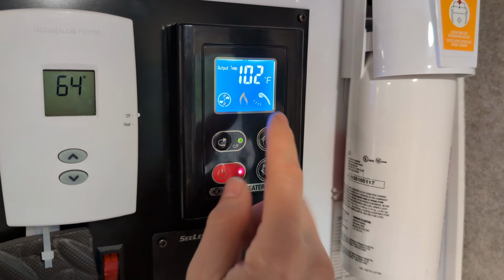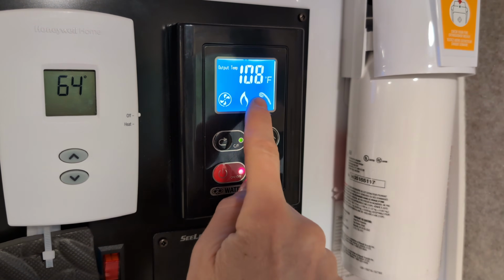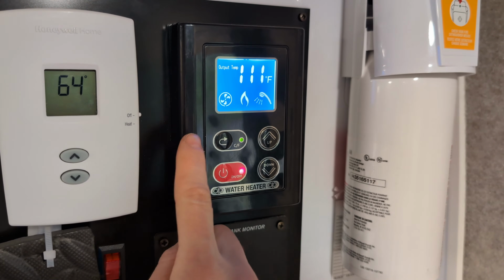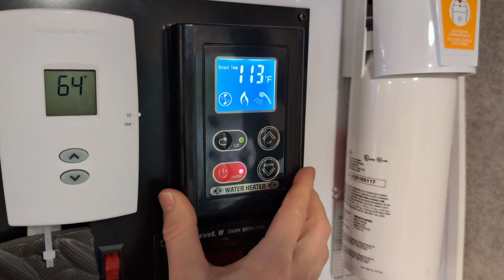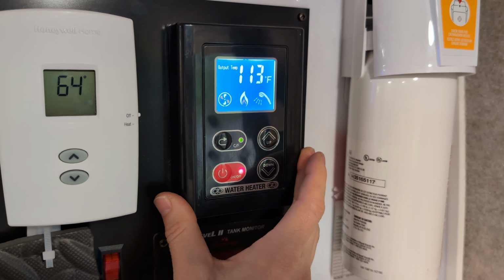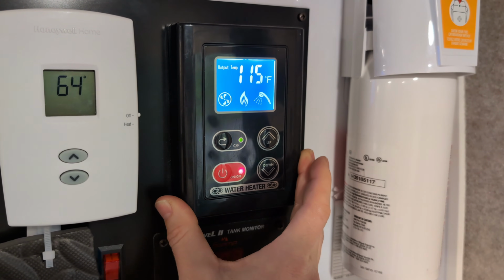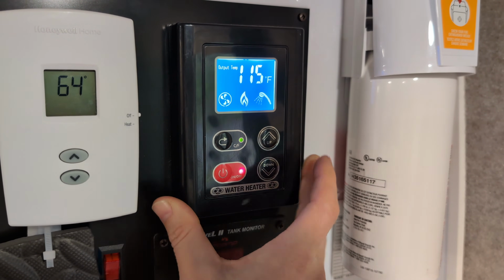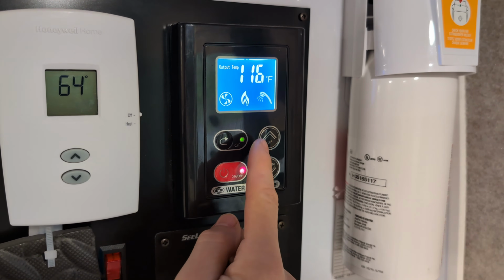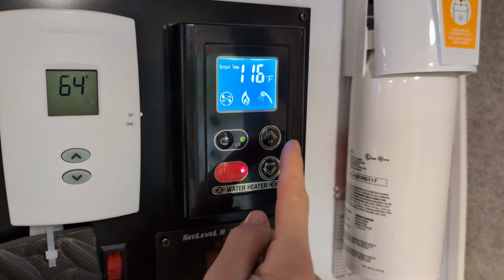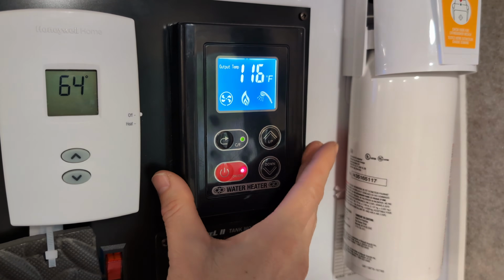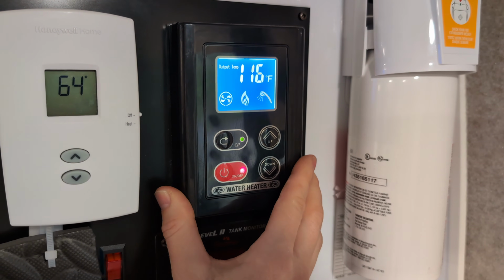If you notice, it takes flow to get the temperature to start rising. These are not based on pressure. When people say they have too low water pressure for their water heater to work, it's not water pressure you need, it's flow. Depending on the flow rate, the more the water is moving through the water heater, the more it's going to heat up the water as you use it.